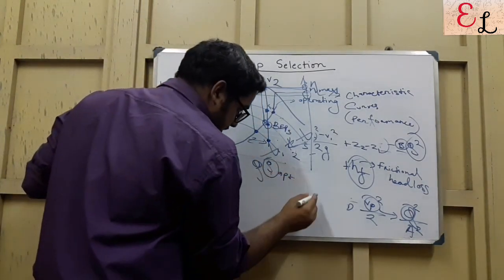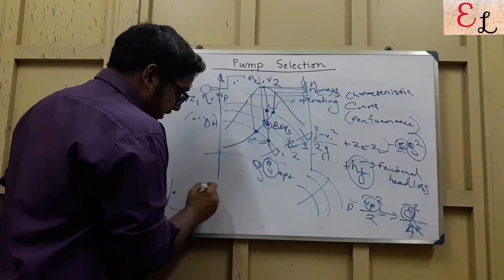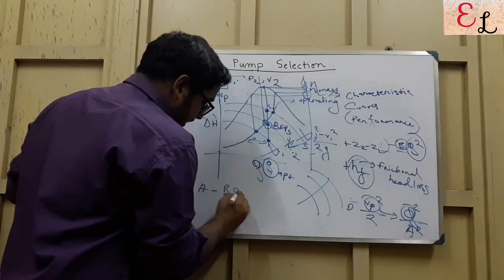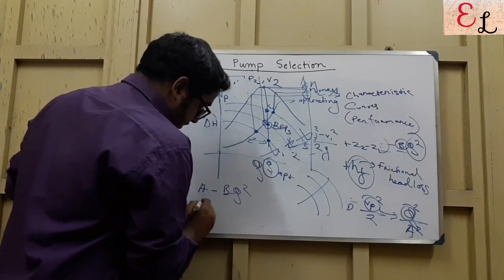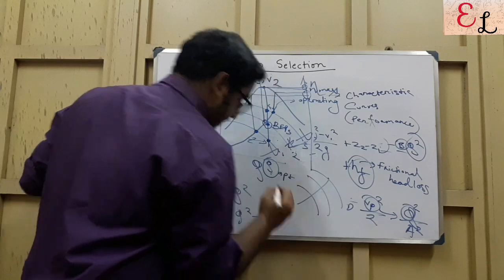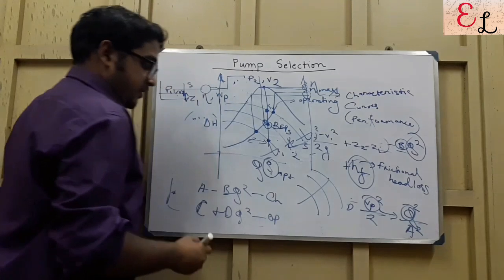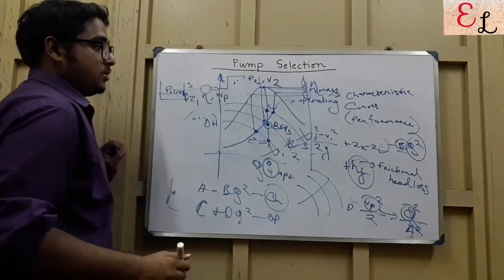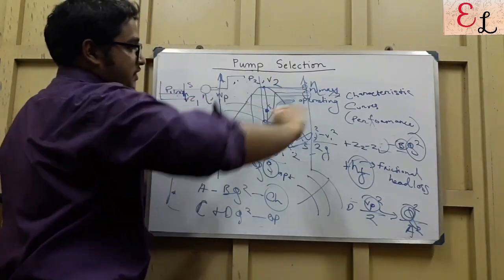So you need to find the cutting of the head characteristic curve and the head operating curve, one being A minus BQ square, another being C plus DQ square. Operating curve is from the equation of energy balance and this is from head characteristic curve. And the best efficiency point is going to be selected. So we are going to select pump 2 here. And this is how the selection is done, referring to the efficiency.